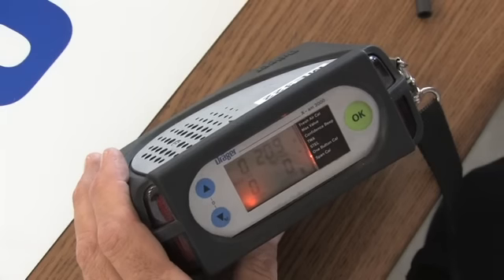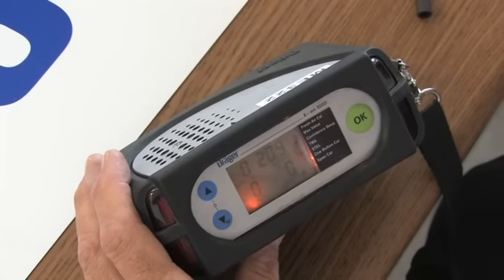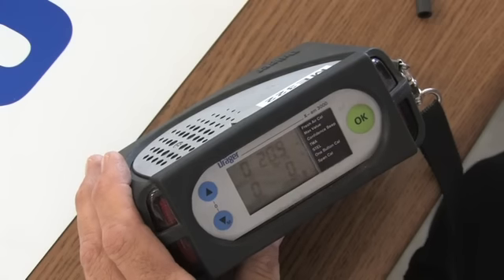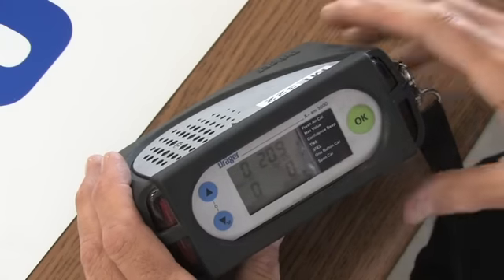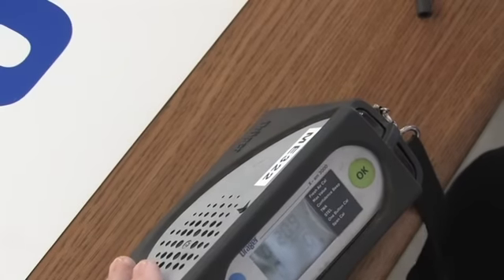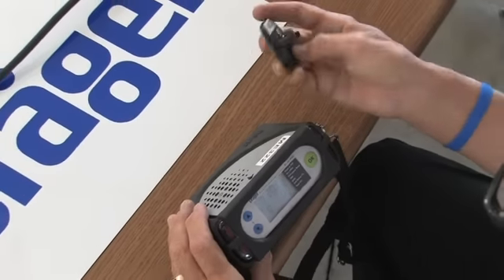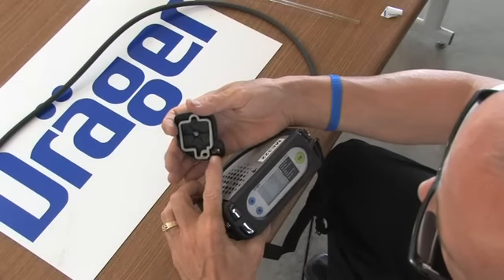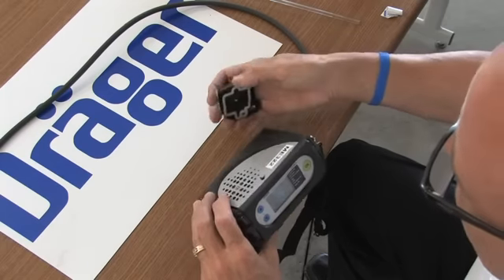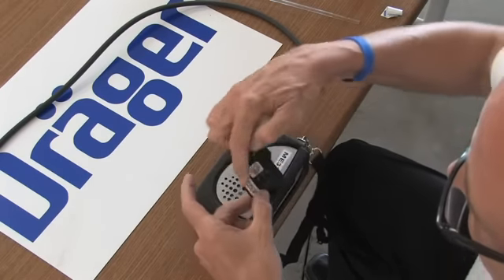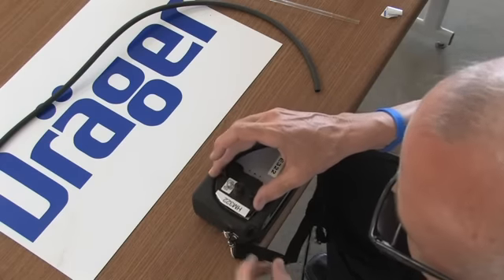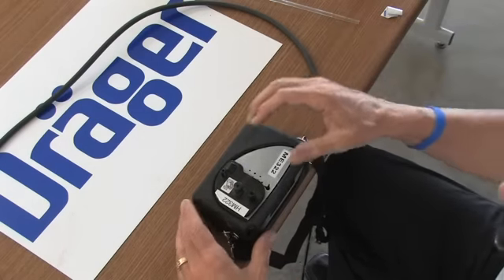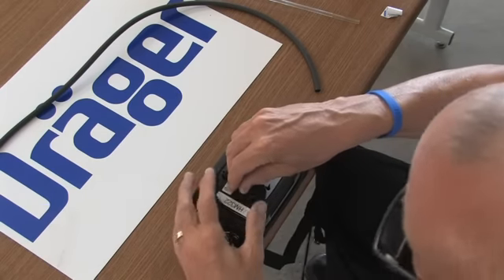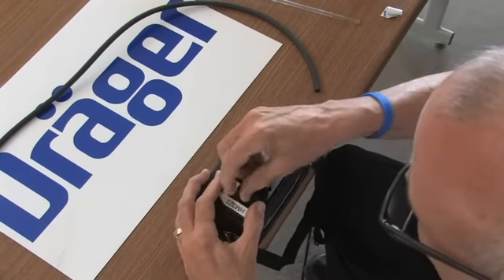And now what I want to do before I use this meter is perform a bump test. Generally this is something I would do after a call, but today I'm just checking out my meters and I'm going to go ahead and give it a bump test because the chief wants to use this meter later on tonight for some testing. So, again, a Draeger magnet. Here's your magnet right here, and it's that magnet that activates the internal pump on the meter. You also see that there's a cutout on this pump plate that parallels the pattern of the rubber boot on the exterior of the instrument.